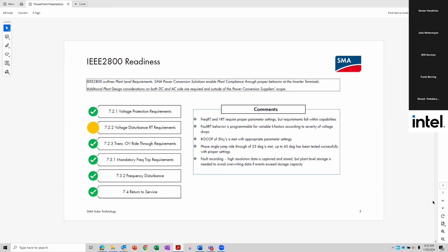Voltage disturbance ride-through is where we have a little bit of a warning, just like the next one mentioned. I think these have to be confirmed for grid strength and various other conditions during an EMT study. Confirmation is needed to conform to the voltage disturbance requirements under section 7.2.2, and I have a further slide explaining that. The transient overvoltage ride-through requirement is new.